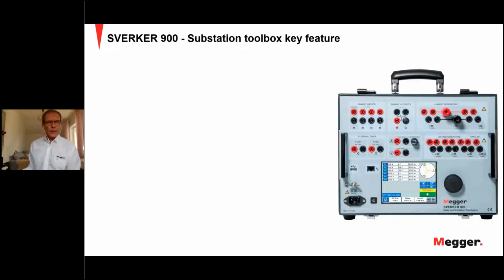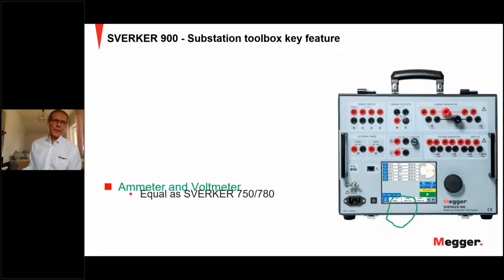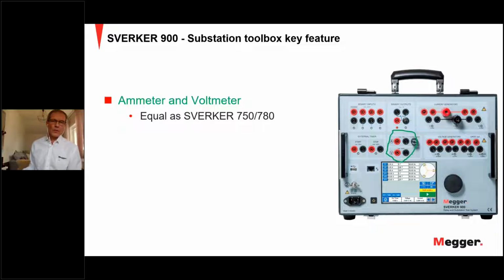And then we have the SVERKER 900, which is also a substation toolbox with a lot of key features to test the complete substation. It also has the ammeter and the voltmeter, equal to what we have in the SVERKER 700 series, which can also measure things like phase angle between these analog inputs and power factor and so on. We also have timers to do the timing of relays, for example, when testing relays.